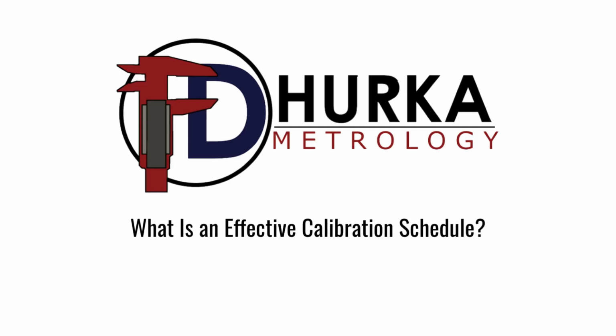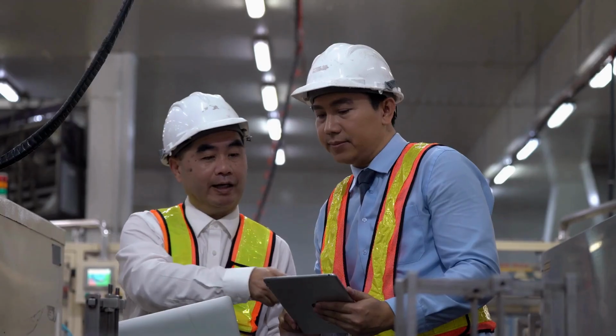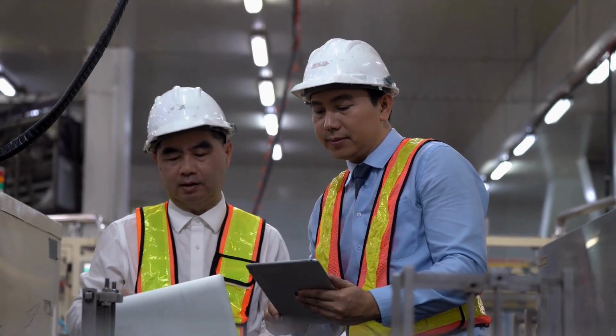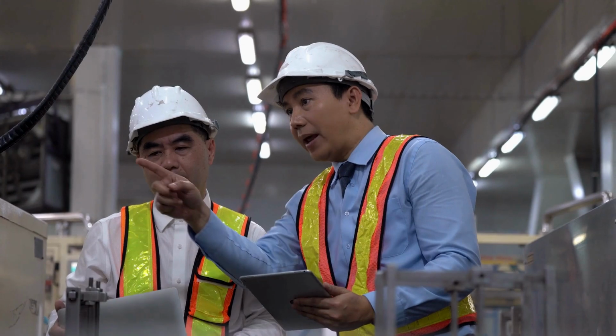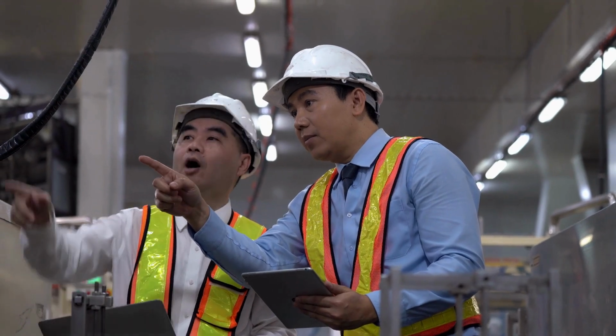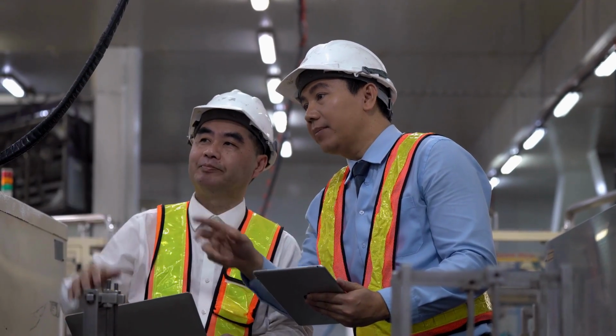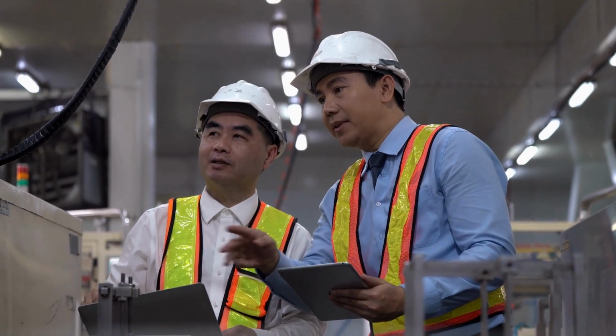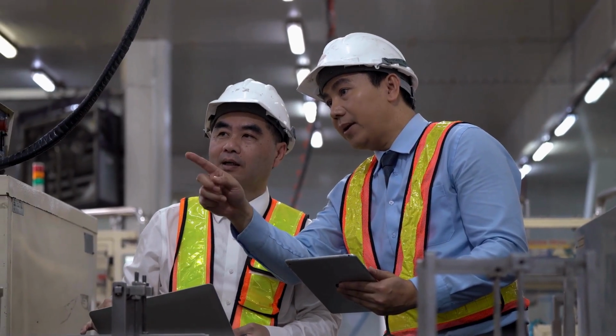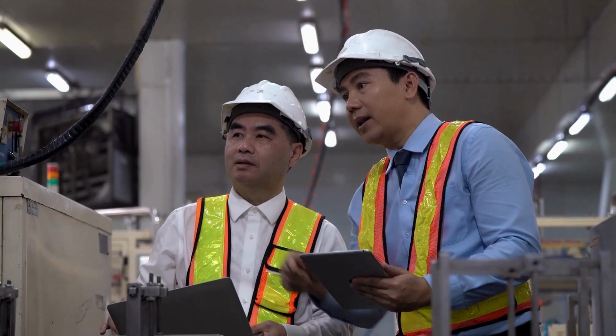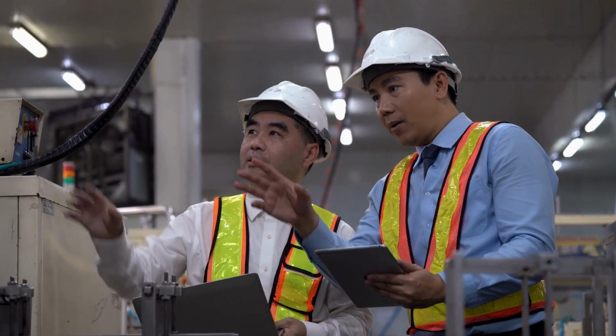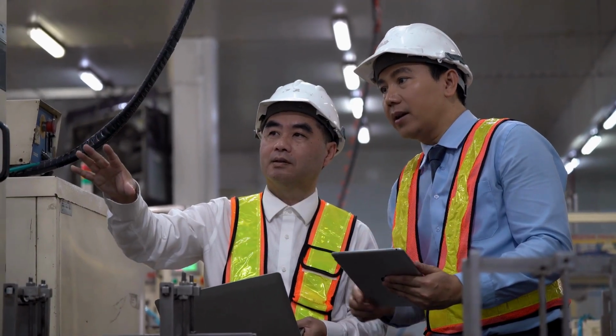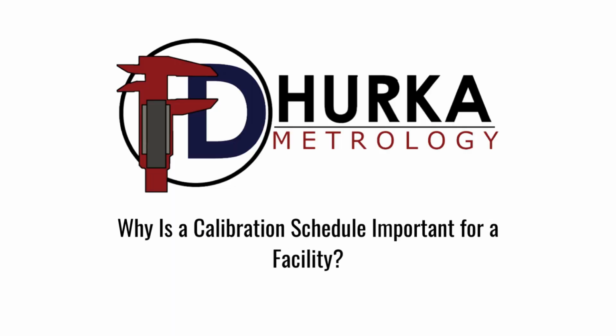What is an effective calibration schedule? An effective calibration schedule is a structured plan that helps a facility determine which instruments need calibration, how often they should be calibrated, who is responsible, and how records are managed, making calibration a planned and controlled process rather than a reactive one. Why is a calibration schedule important for a facility?